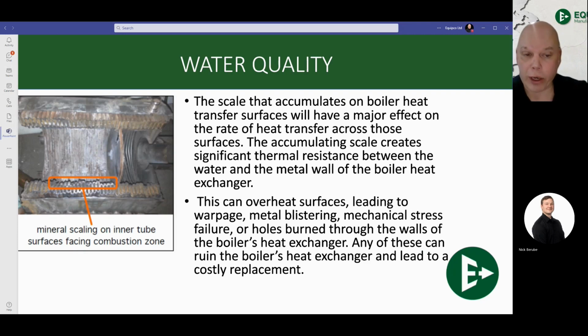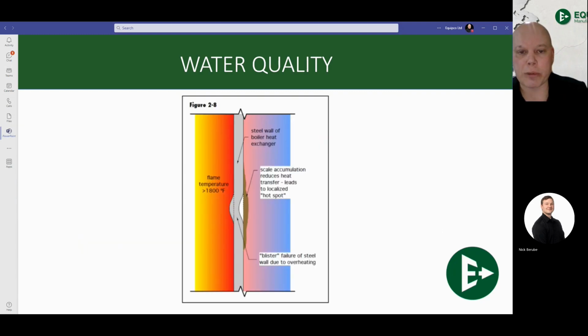I showed you on the fire tube how it accumulates on the inside of that one, and this is how it accumulates on the inside of a water tube heat exchanger. Fire tubes are more forgiving to bad water quality, whereas with these water tubes, that's a very small water chamber going through there. So any sort of buildup will lead to a low flow application, and you're going to crack your heat exchanger very, very quickly. And again, that is not going to be a warranty replacement. That's going to be something on the homeowner that they need to pay for.